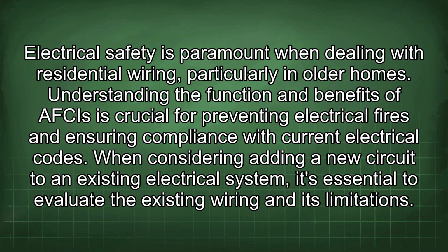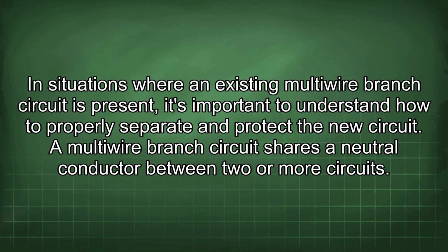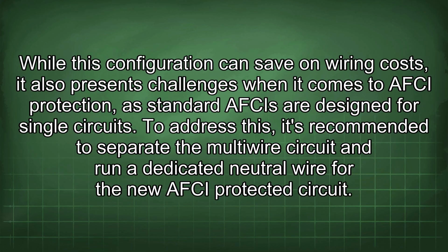When considering adding a new circuit to an existing electrical system, it's essential to evaluate the existing wiring and its limitations. In situations where an existing multi-wire branch circuit is present, it's important to understand how to properly separate and protect the new circuit. A multi-wire branch circuit shares a neutral conductor between two or more circuits. While this configuration can save on wiring costs, it also presents challenges when it comes to AFCI protection, as standard AFCIs are designed for single circuits.